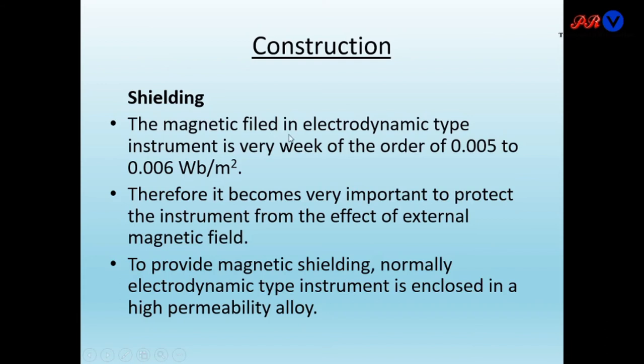The magnetic field produced by the fixed coils is very weak because of the air-core coil. The magnetic field in electrodynamic type instruments is very weak, of the order of 0.005 to 0.006 Weber per meter square. Therefore it becomes very important to protect the instrument from external magnetic fields. Magnetic shielding is provided by enclosing the instrument in a high-permeability alloy casing.